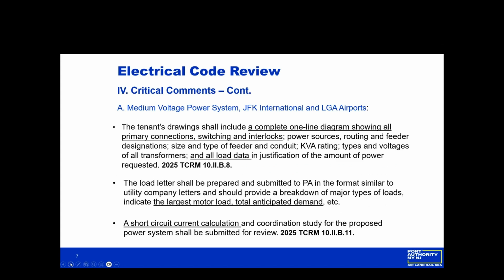A load letter shall be prepared and submitted to PA in the format very similar to utility company letters, and should provide a breakdown of major type of loads, indicated the largest motor load and total anticipated demand, etc. A short circuit calculation for the medium voltage system. Coordination study for the proposed power system shall be submitted for review. Next.